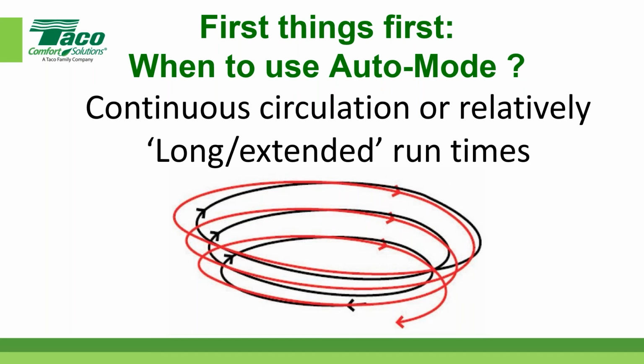But my point is, a lot of these algorithms are set up to not kick in and make any changes until the pump's been running a sizable amount of time. So what I'm getting at is, if your zones are going to call for heat, they're going to open, the pump's coming on, and you're going to satisfy that zone in, like, 5 or 10 minutes and shut back off again, you've not given that algorithm enough time to make a decision whether to step up and down on the rungs of the ladder, right? So just understand that concept.